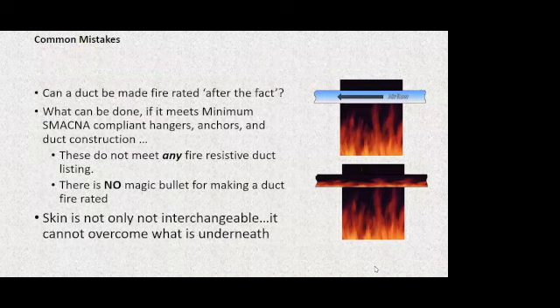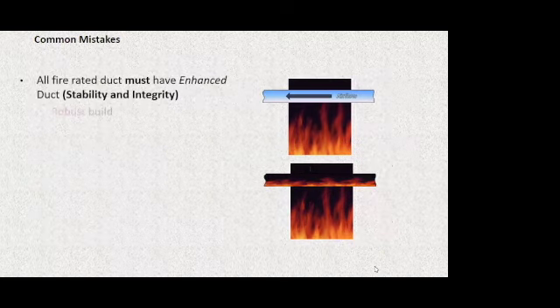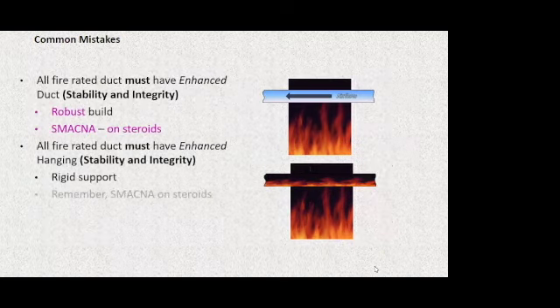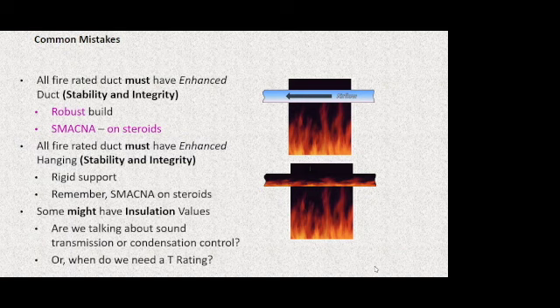We need to know it up front, because we know that SMACNA minimum, hanging systems, anchors, joining methods, and duct construction do not get us to fire duct land. We're going to look at some listing cards and find that there's none of them that have an underlying backbone like that. And the skin matters no more than the ability of the skeleton to hold it up. So it's going to be rigid trapeze supports. It's going to be SMACNA on steroids. It's going to be very, very robust. And we may or may not need insulation value.